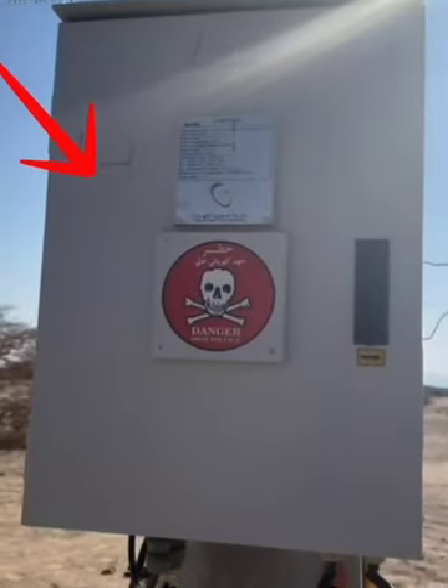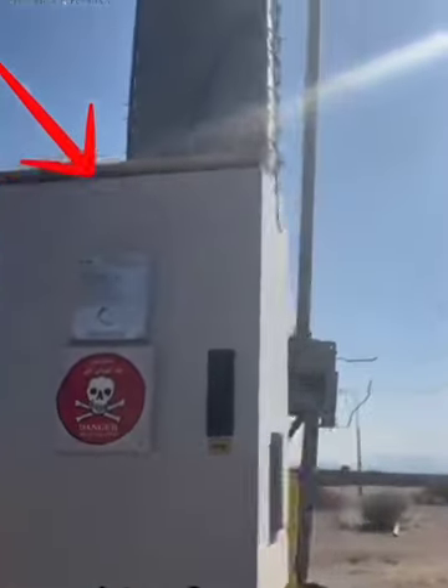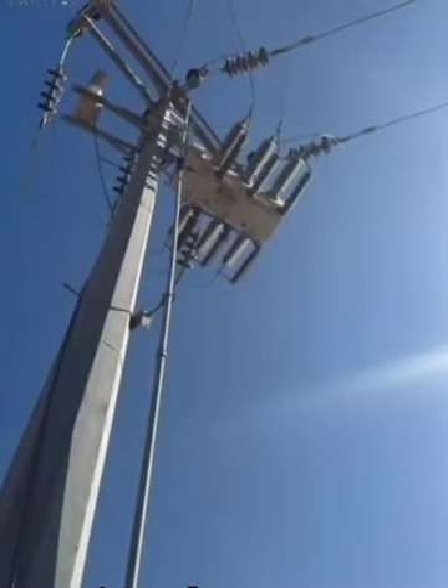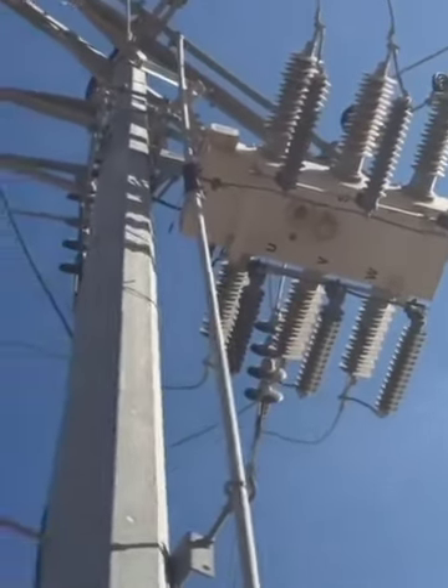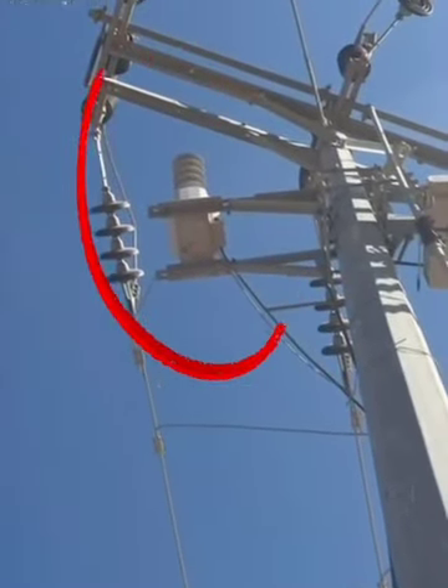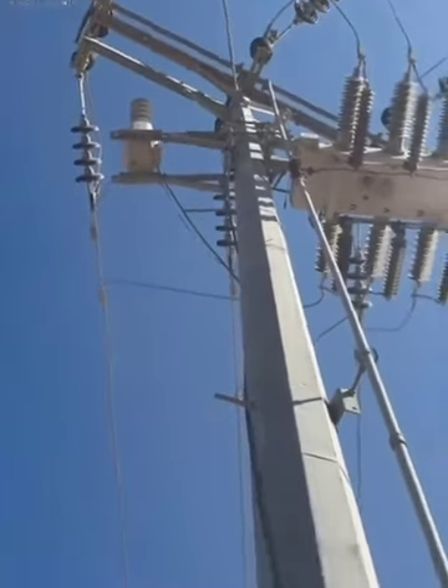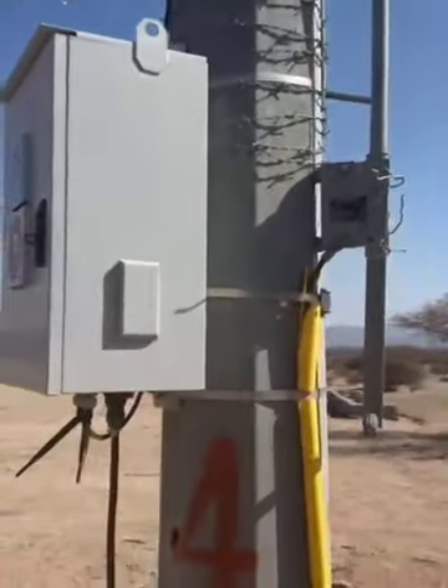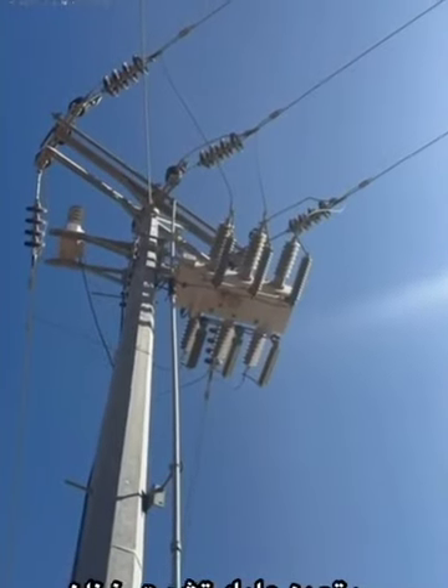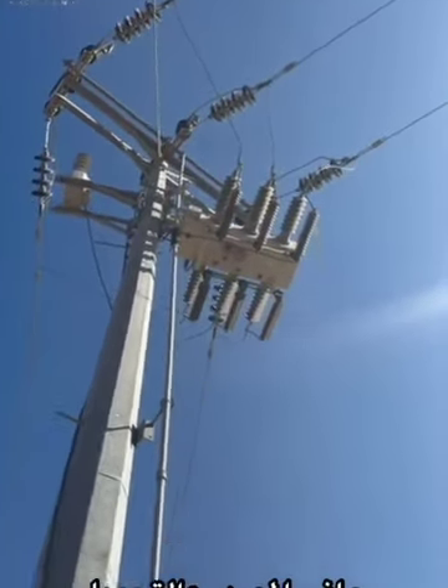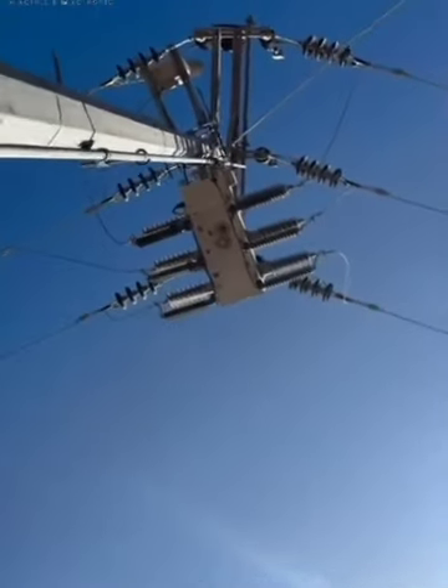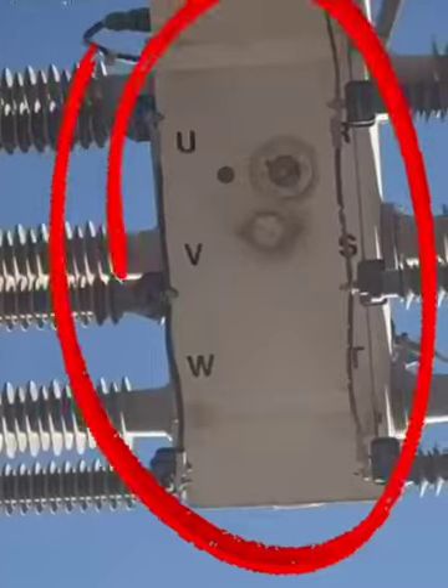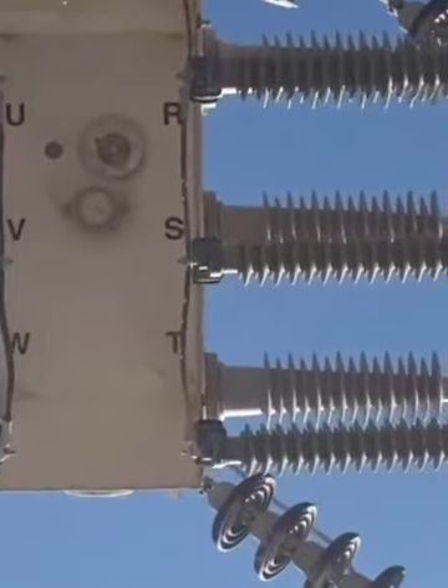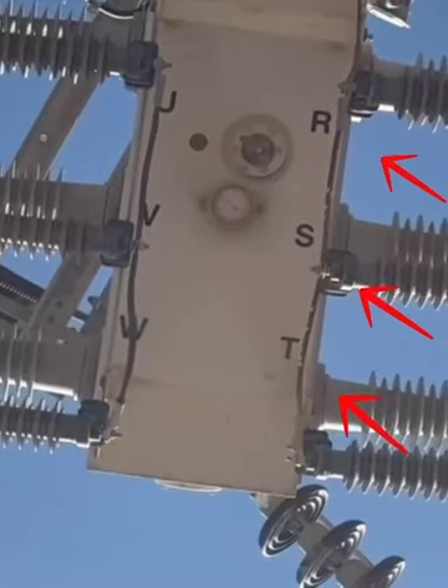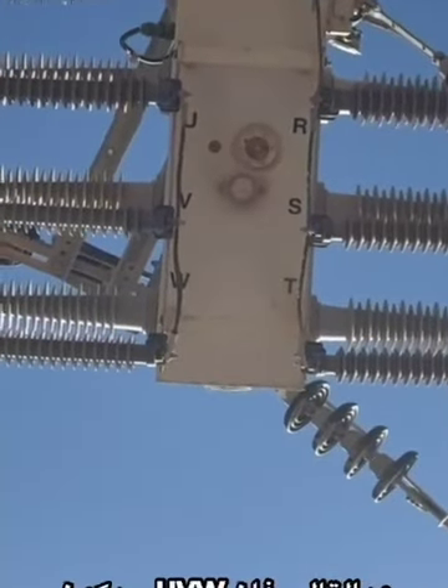So this is the ETMFC 610 controller, having a set with the LBS tank, you see here, and the VT, or the PT, the potential transformer. First of all, when you install the product, you'll have to install the LBS tank on the source and load side exactly. Under the tank, you will see the UVW and the RST. The UVW will be the source side and the RST will be the load side.